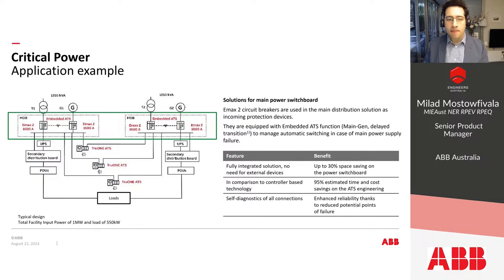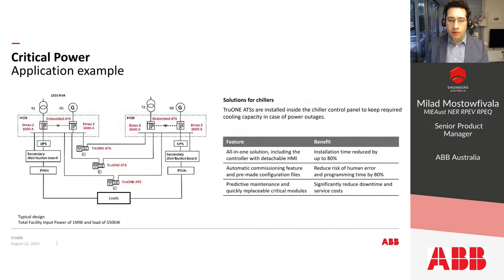As you can see, they were able to utilize the circuit breaker based automatic transfer switching in the connection between the transformer and the generator side. They were able to utilize a 1600 amp circuit breaker sizing for this facility. And what was very interesting for this particular project was the simultaneous use of the circuit breaker based automatic transfer switching for this critical power application, together with the TruONE ATS system. And that was quite successful for the end client within this project. So that was the first reference design example as a critical power application reference.